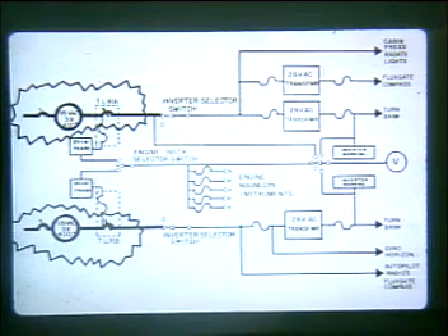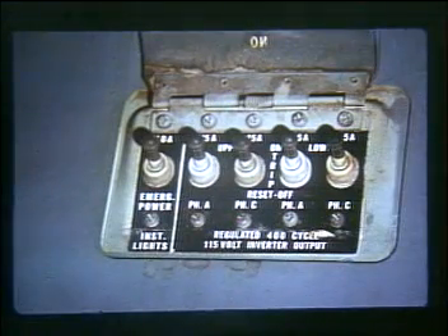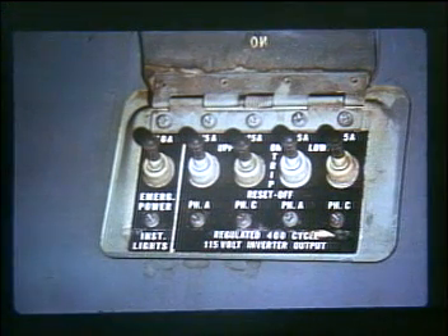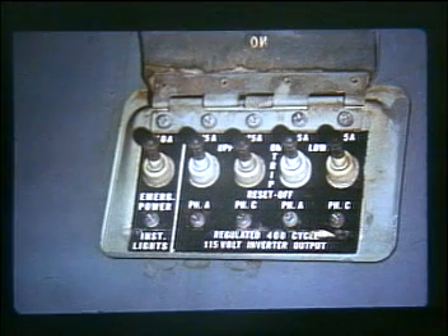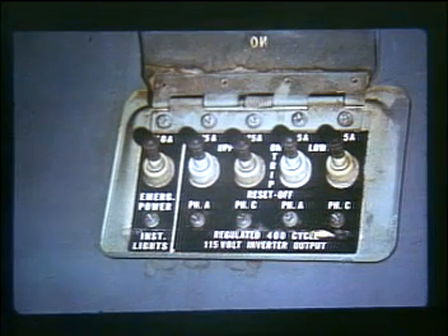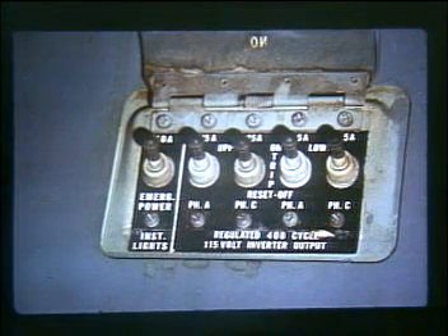There are 4 phase breakers on the throttle lock relay box, 2 for each inverter. The throttle lock relay box is located to the left and behind the captain's seat on the bulkhead. 4 of the circuit breakers on this box protect the A and C phase output of the upper and lower inverters. The 5th circuit breaker is for the emergency instrument lights, discussed in the DC electrical presentation.